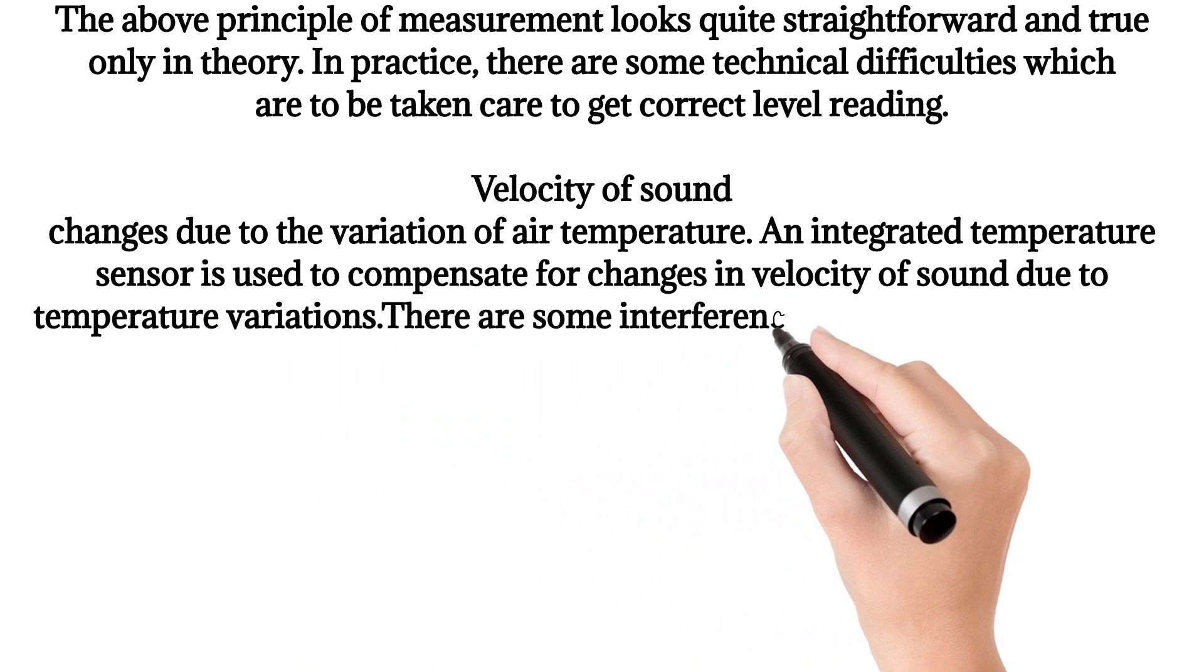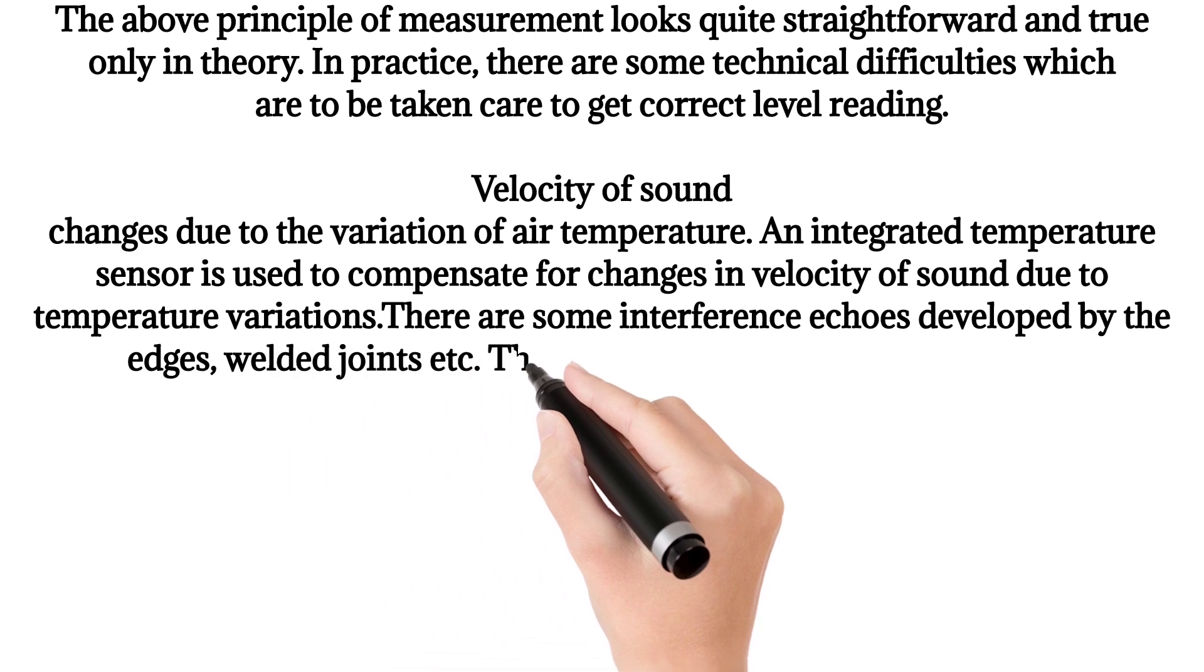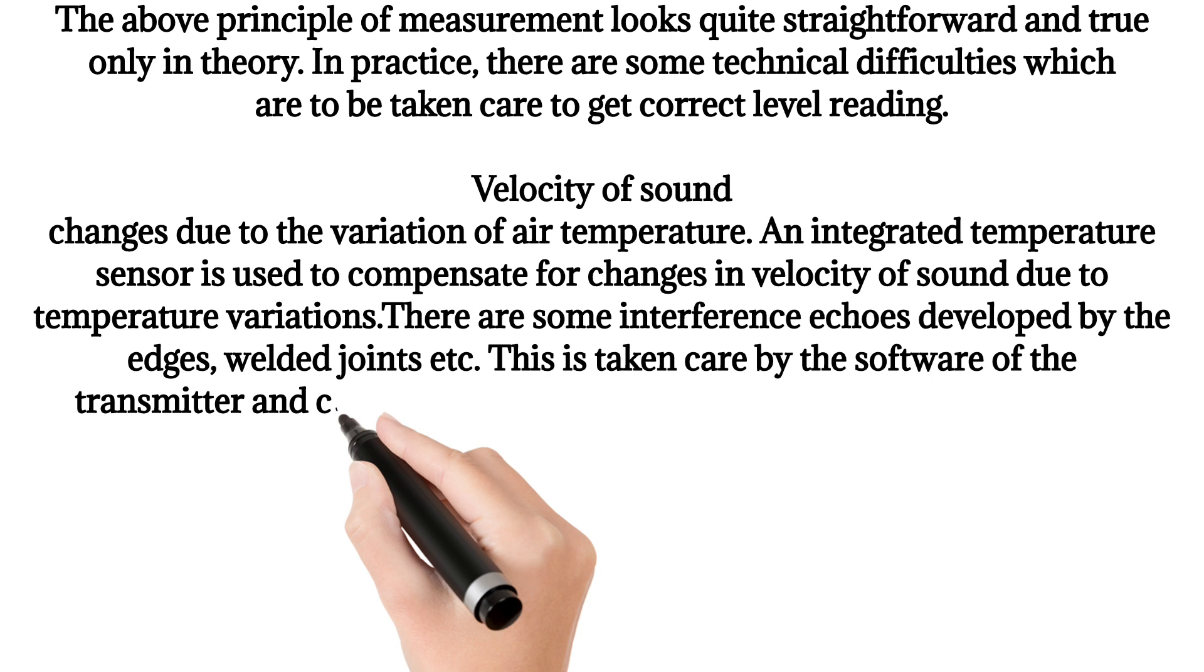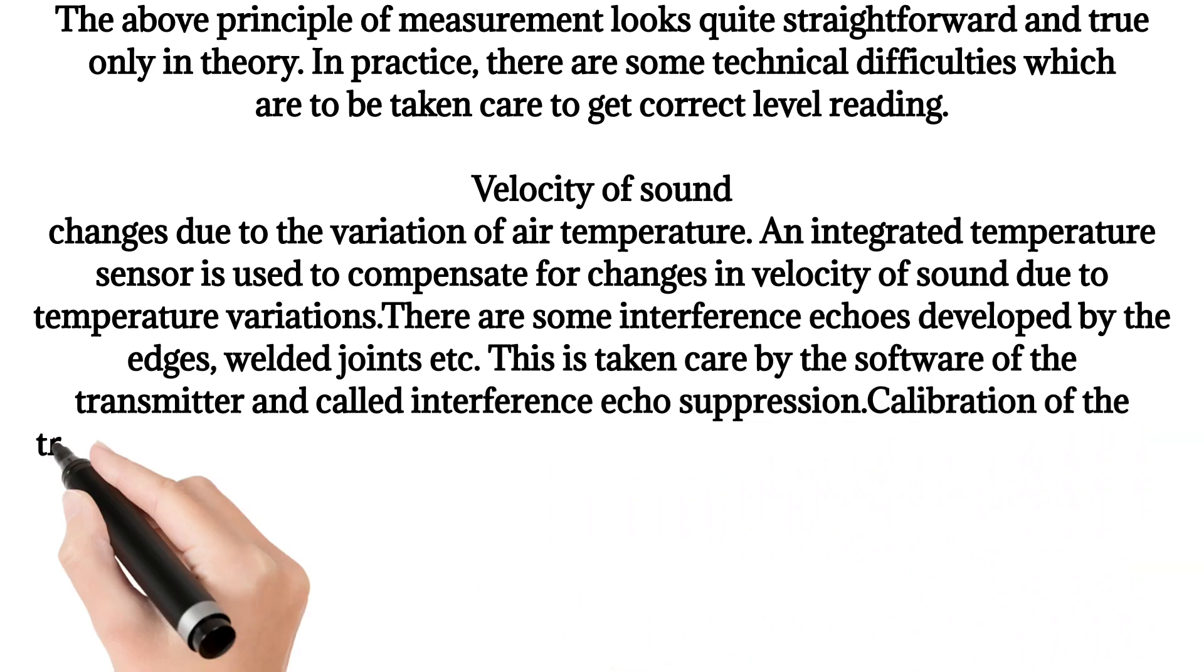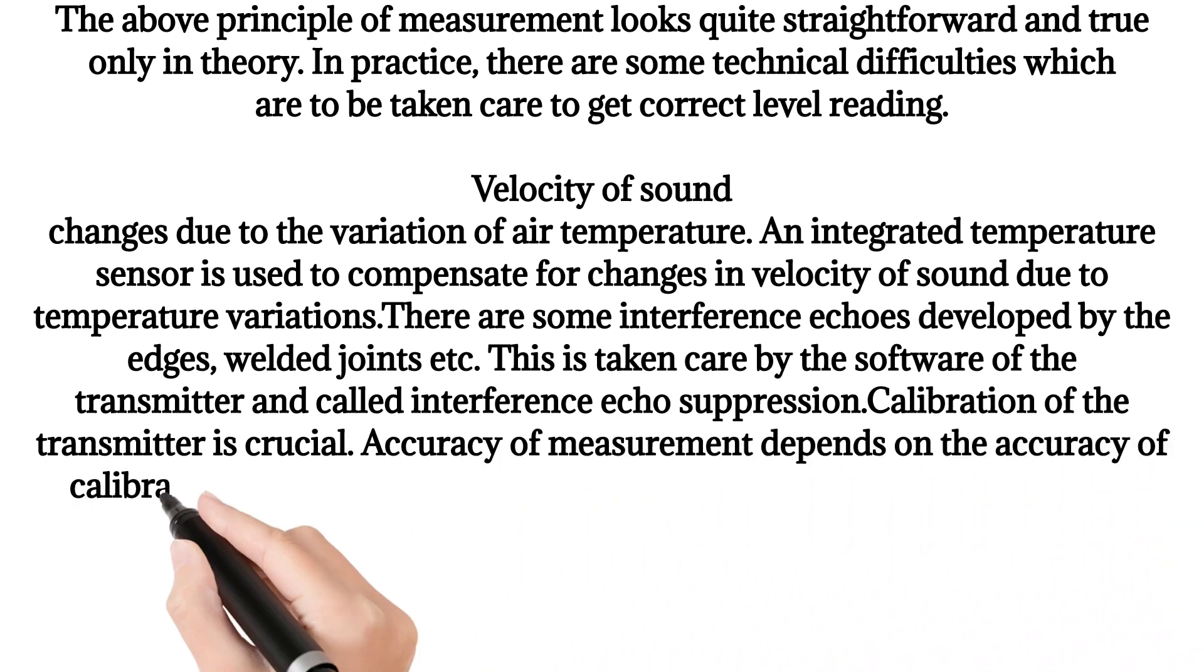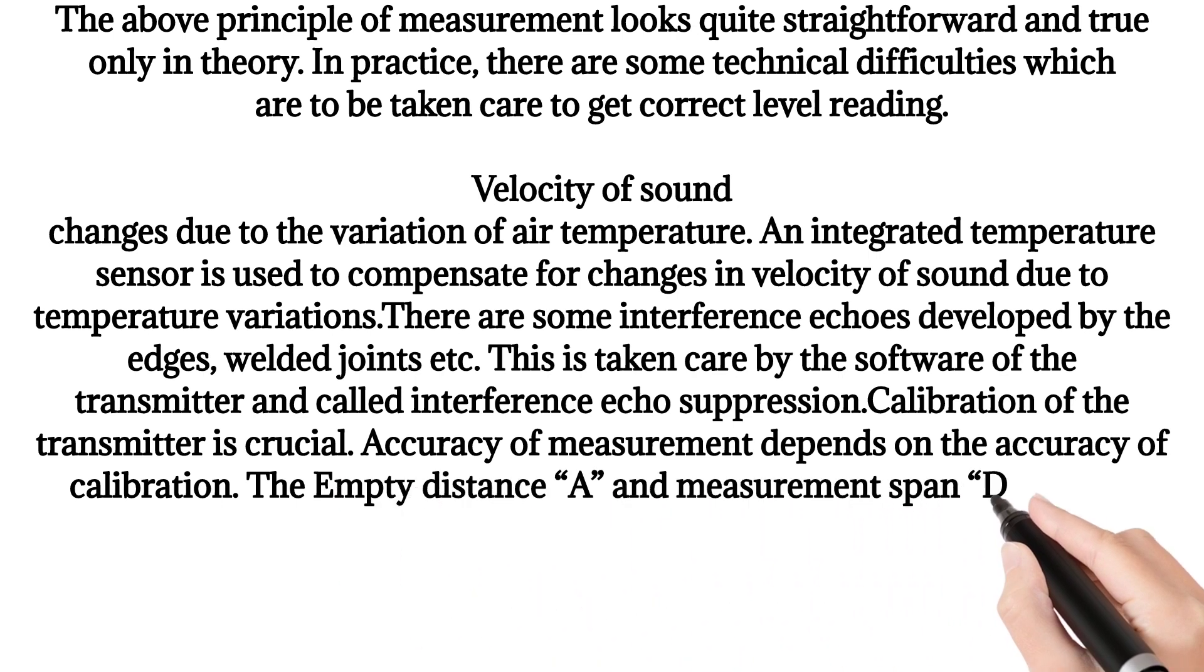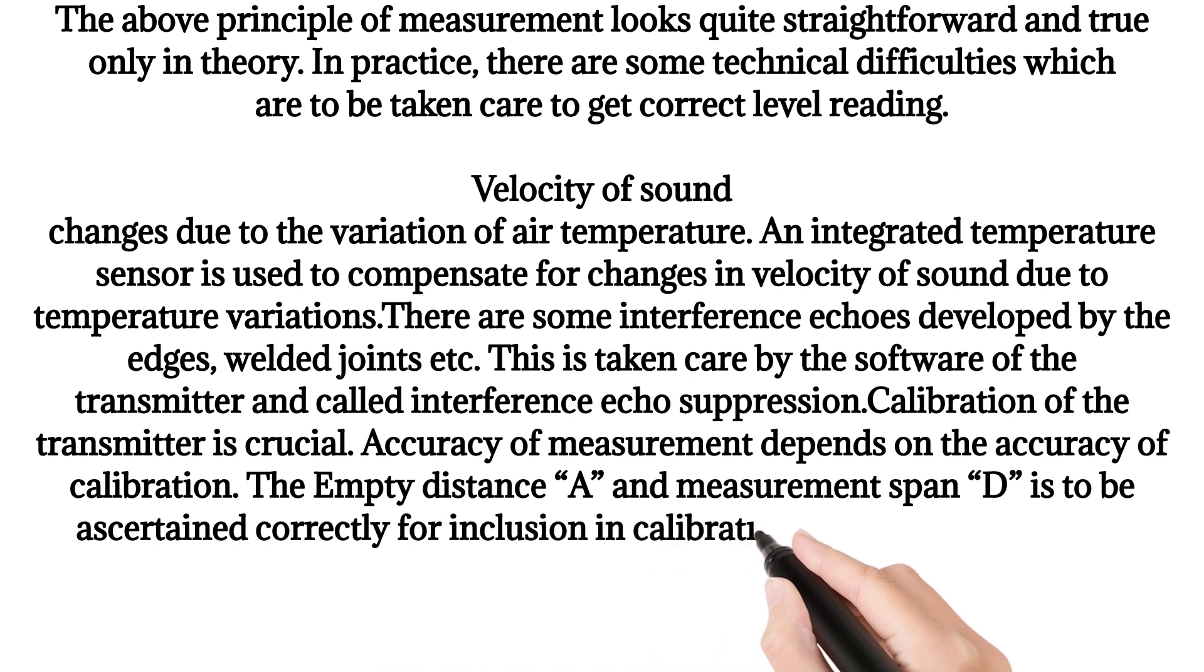There are some interference echoes developed by the edges, welded joints, etc. This is taken care of by the software of the transmitter and called interference echo suppression. Calibration of the transmitter is crucial. Accuracy of measurement depends on the accuracy of calibration. The empty distance A and measurement span D must be ascertained correctly for inclusion in calibration of the transmitter.